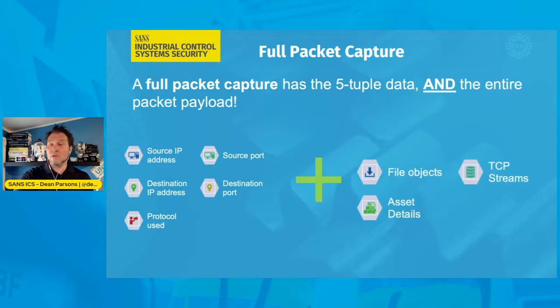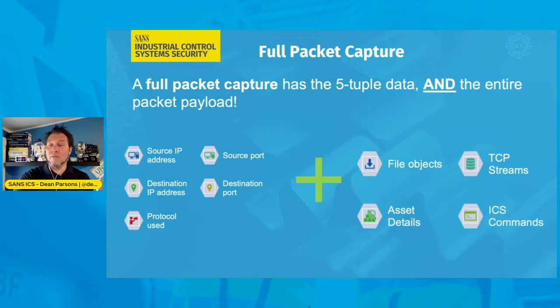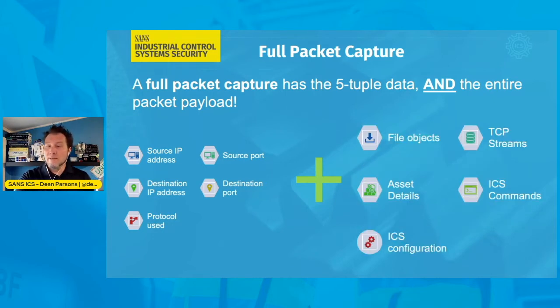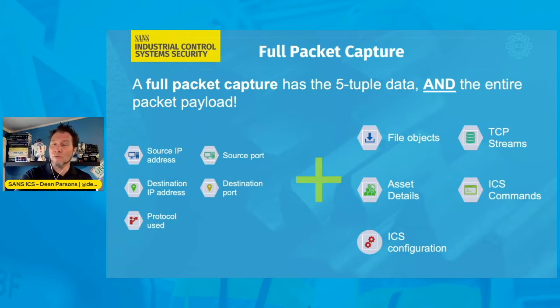Beyond that, you can get information such as the asset details on the network, and beyond that, the specific ICS commands being used. In the case of Modbus TCP, for example, with the full PCAP you get to see the function codes being used from the controllers to the HMI and so forth. You could also get the ICS network configuration from some devices as well.